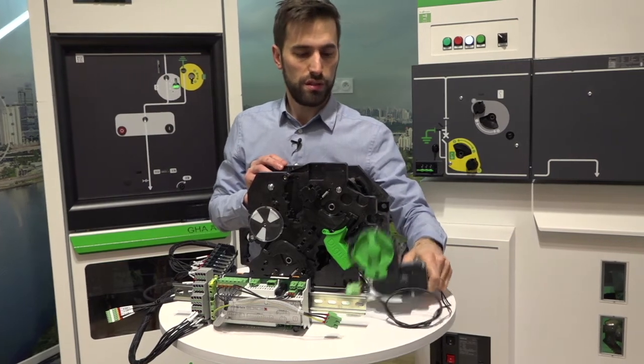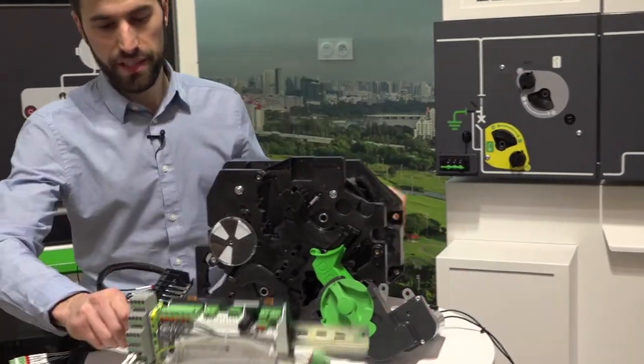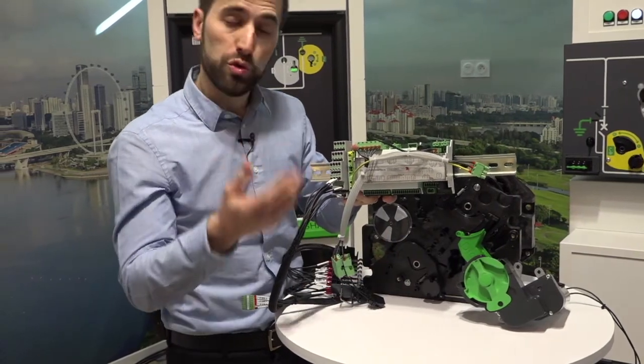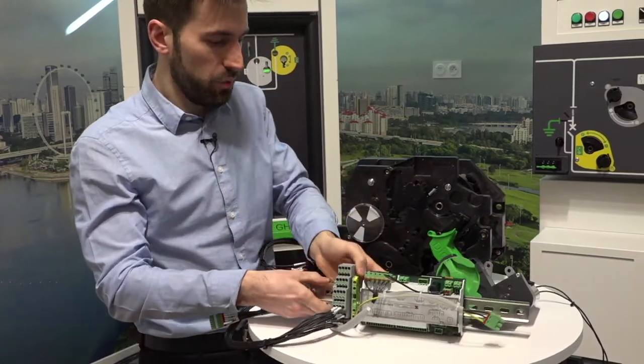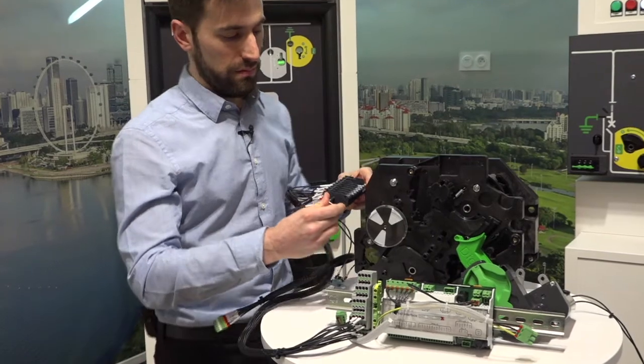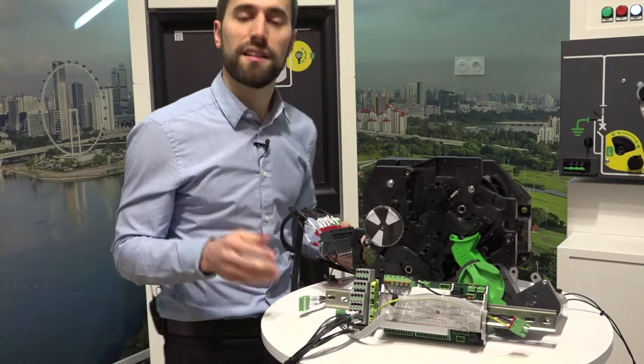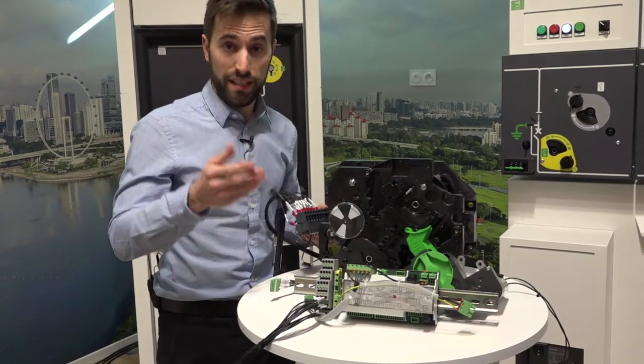Then we have, of course, the plug-and-play motor. We have a specific motor control board, PCB, which is used to control and energize the motor, and is used as well to feed the opening and closing coils for those units having single latching and double latching mechanisms, right? And we have the auxiliary contacts for line and earthing switch. As you can see, this is a pre-wired kit, so you order one reference and everything already comes integrated to make the installation easy.